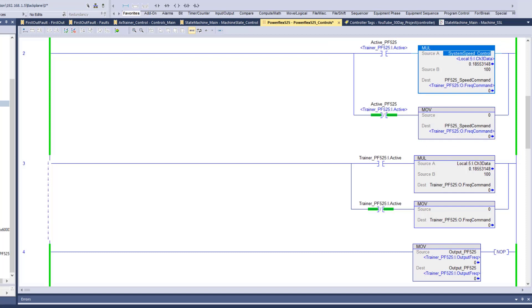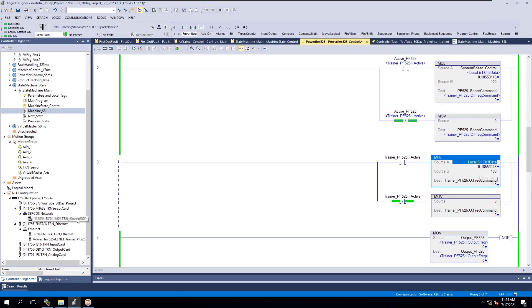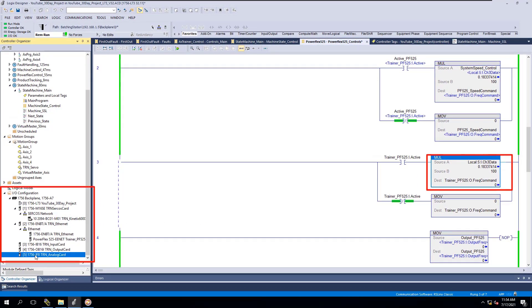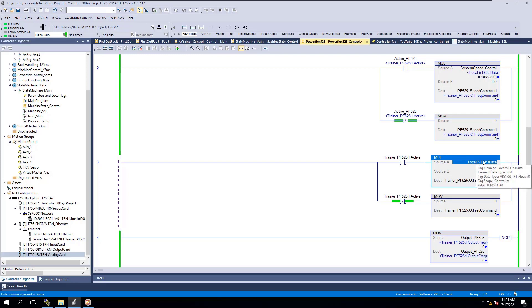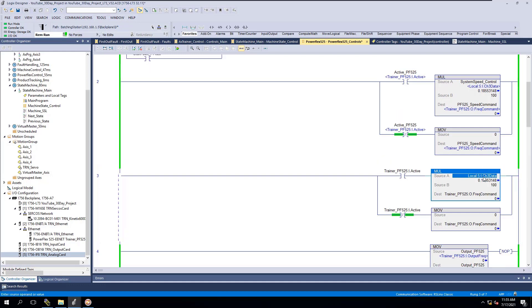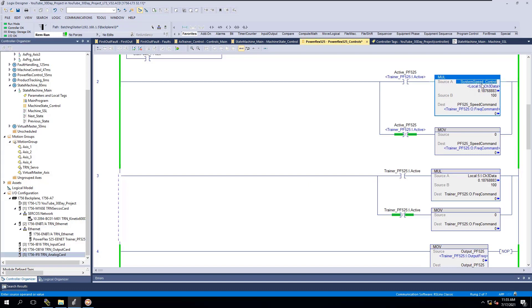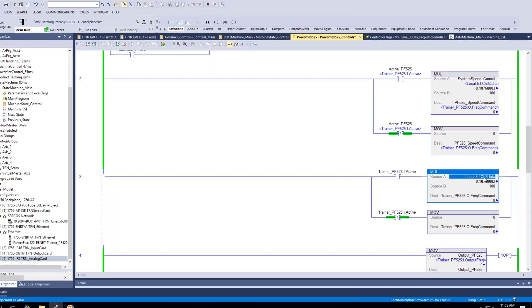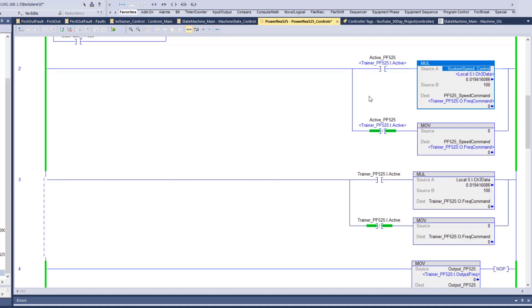Now, if I come in here and just put the actual real world IO, for this instance, it would be Card 5 in the local rack, right? Some of these systems get really huge and instead of the local racks, they have remote racks. When it comes to remote racks, that could get really big and you don't know where it's located at. So if I say local 5, Channel 5 and then our local 5 input channel 3 data, that's on that card. But if I said this is the speed command, that tells you what it is and what it's doing. But if I actually told you what it does in the program, which is the speed control, let me just turn this knob, which is going to be the actual speed command for that. You can see that data changing.